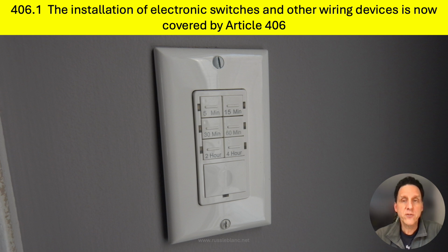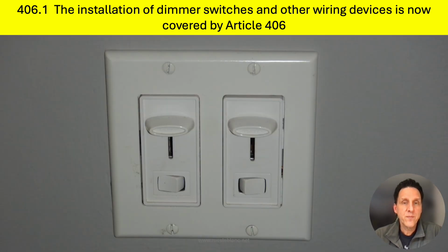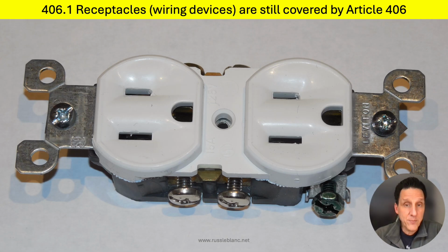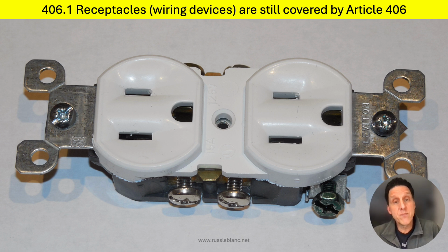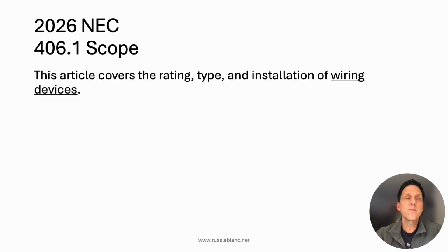That's an electronic switch, actually. And then dimmer switches. Receptacles will still be covered by 406. So all of those wiring devices will now be covered by 406. Even all those switches, all those snap switches, electronic switches, and dimmer switches, which previously were covered by 404, will now be relocated into 406. Again, the scope of 406 is going to be this: the article covers the rating, type, and installation of wiring devices.